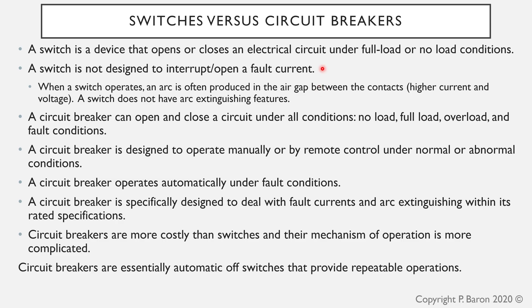A switch is not designed to interrupt or open a fault current, because when a switch operates an arc is often produced in the air gap between the contacts, especially when the current and voltage are higher. A switch does not have arc extinguishing features like a circuit breaker, so the arc may be present for some time and it often damages the switch contacts.